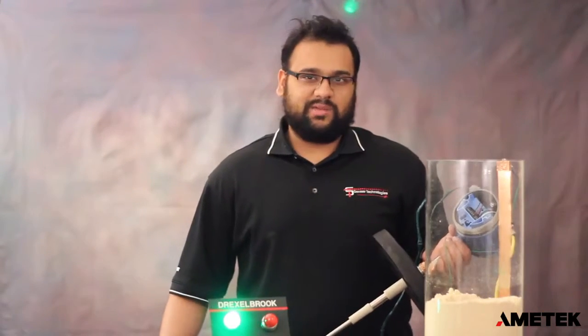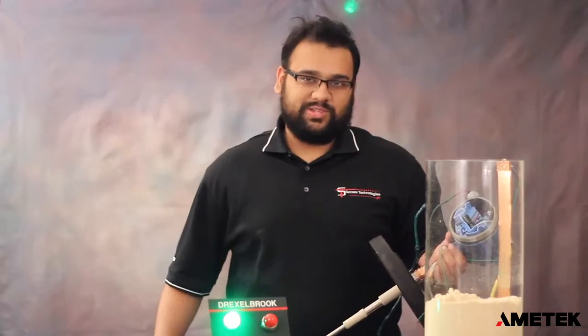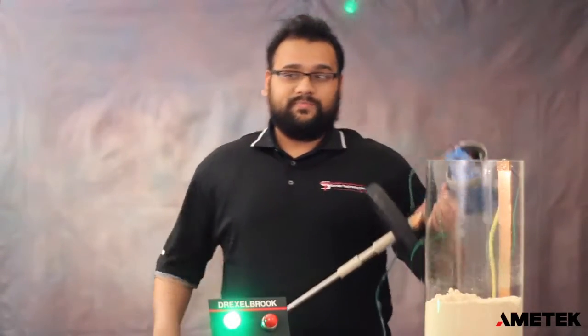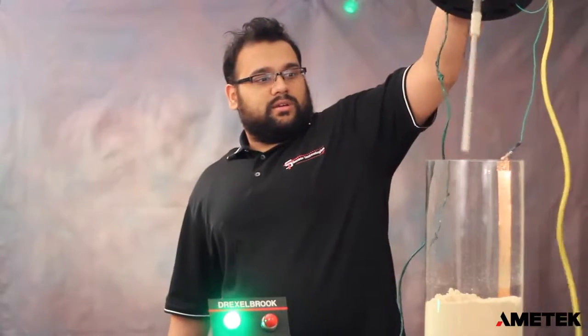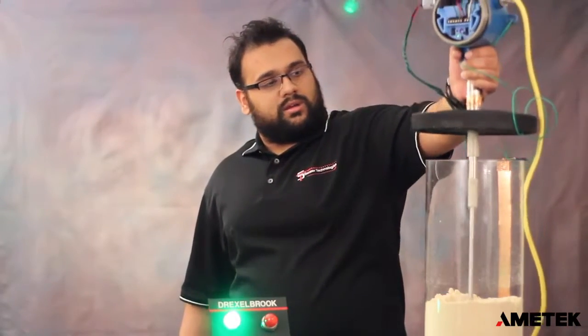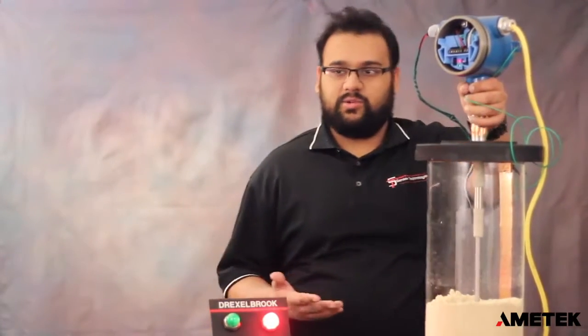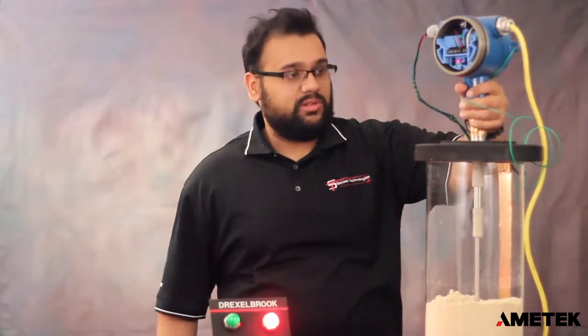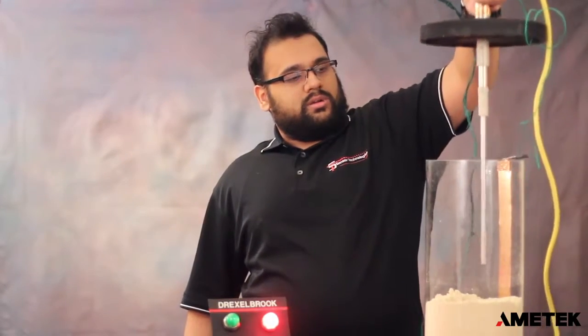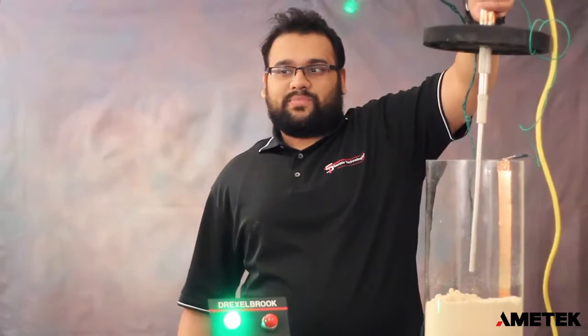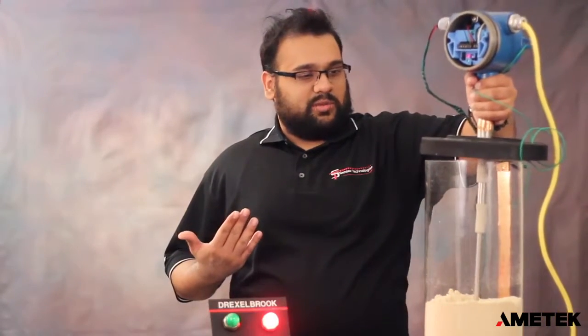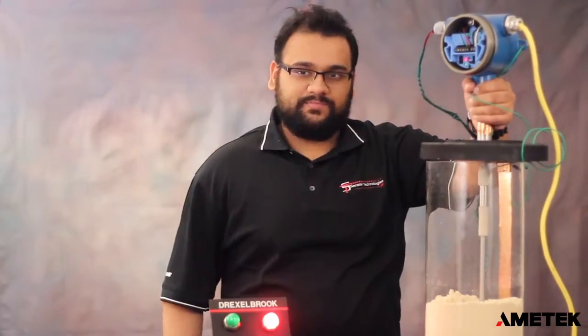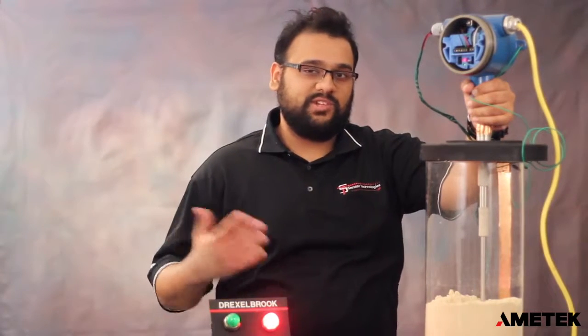Okay, so now that we've done our calibration, the last step is to make sure that our unit goes in and out of alarm properly. In our tank here, we have about 8 inches of sawdust, so we're just going to raise and lower our point and see if the unit goes into alarm. Take our unit, go down, goes into alarm just as it should when touching the material. We'll raise it out, and it comes out of alarm. So this means our unit is working properly and our calibration was done correctly. And that's all there is to it. We hope you enjoyed this tutorial.